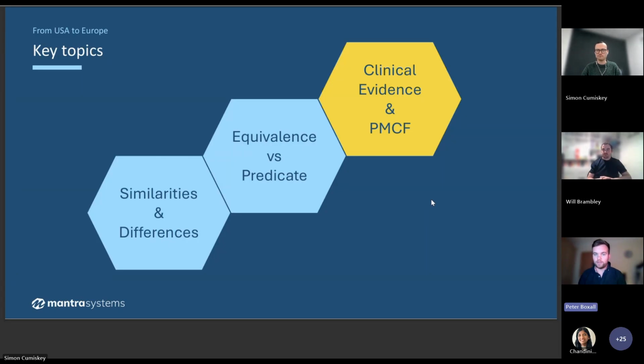And we need clinical evidence of risk, so adverse events, side effects, risk data that's come through from complaints from users, for example. And we need to show, in terms of risks, how severe are those risks? How frequent are they? In terms of benefits, what's the magnitude of the clinical benefit to the patient? Again, how frequent is the benefit associated with use of this device?